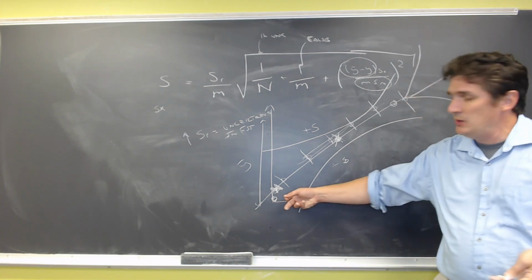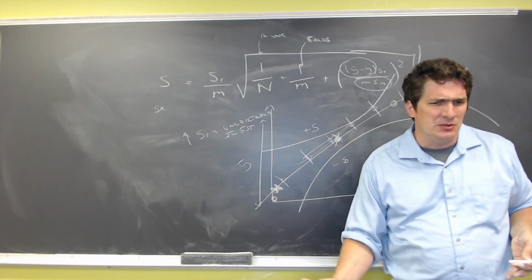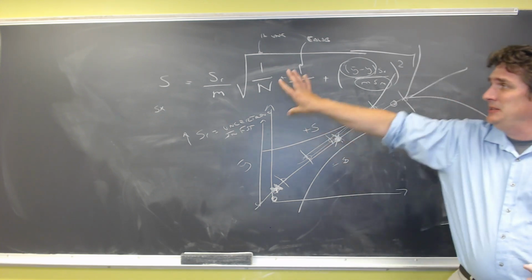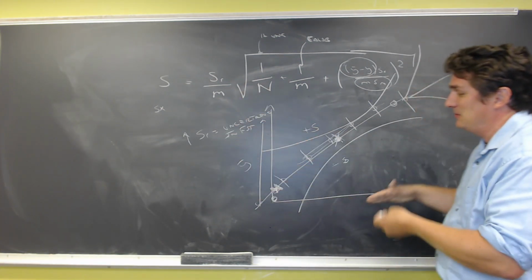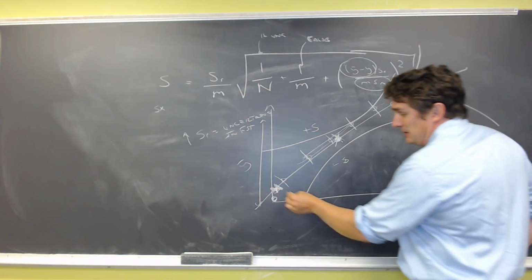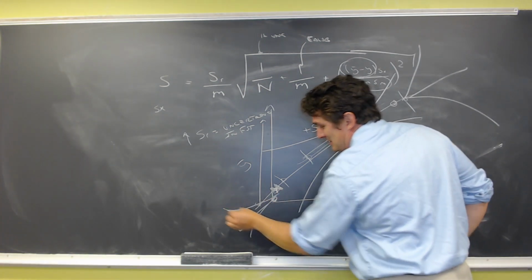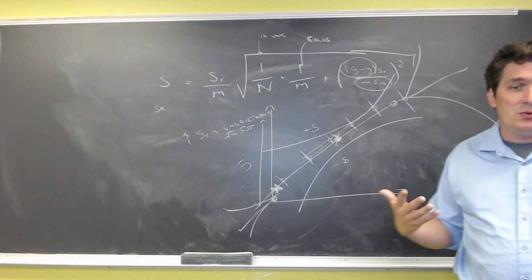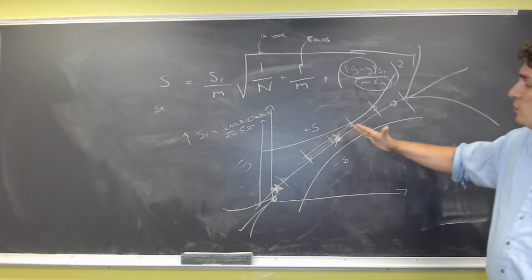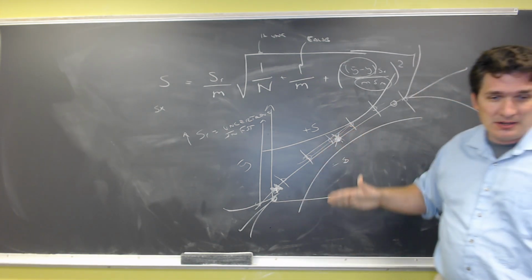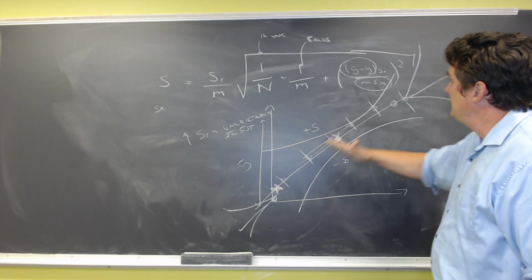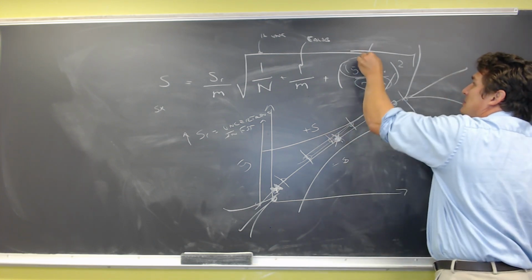Now you can turn around and say, well, down here we know it's 0, we can't get negative. Here's the thing, your stats tests don't know that. We don't know where you measured in your calibration curve. For all we know, you ignore the 0. But it's going to have to make the same assumptions that down here we don't know what the curve does. The more we are in the center of a linear function, the more confident we are that function is linear. But as we start getting towards the edges, we expect our uncertainties to get bigger by merely the fact that we're just not as confident where we're measuring.